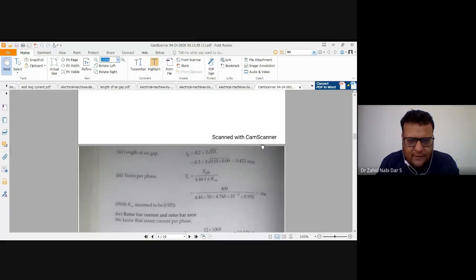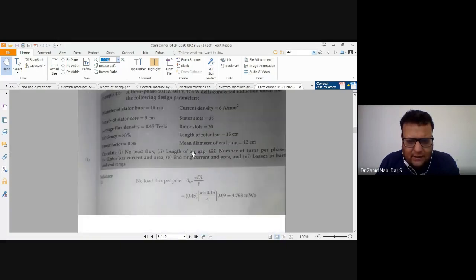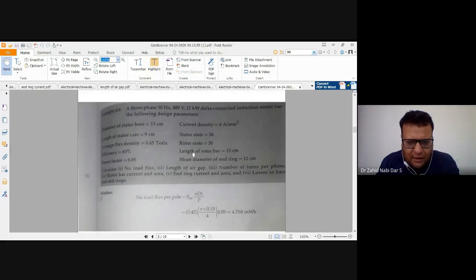0.432 millimeter. Okay. One more important thing here is the BAV value, which is not here, that is average flux density. So you can write here this BAV value is equal to 0.45 and the number of poles is equal to 4. One more thing, you can calculate also the number of poles. How you can calculate? See, NS is equal to 120 F by P. So NS is equal to 120 F by P, or in other terms, 120 into 50 divided by P.